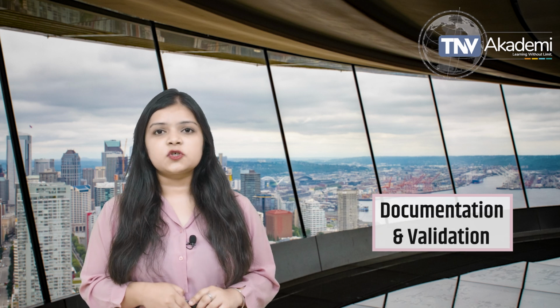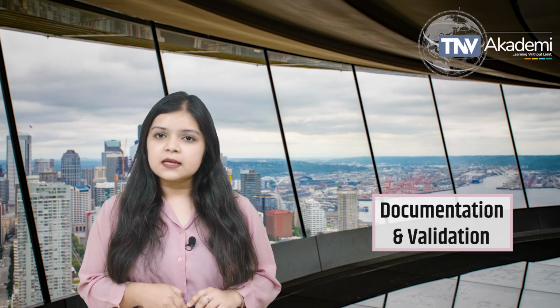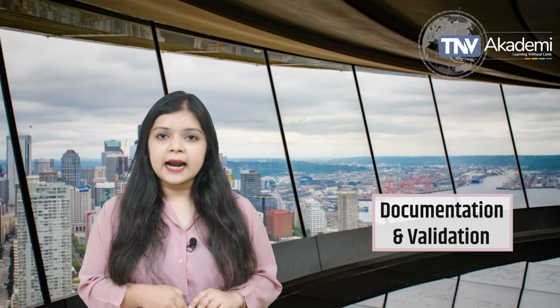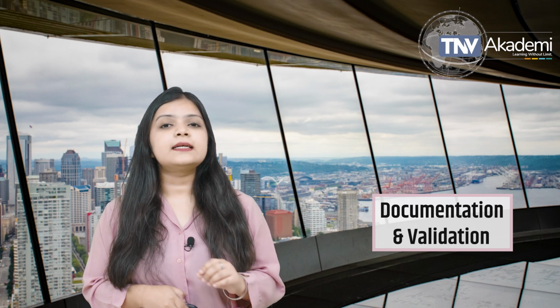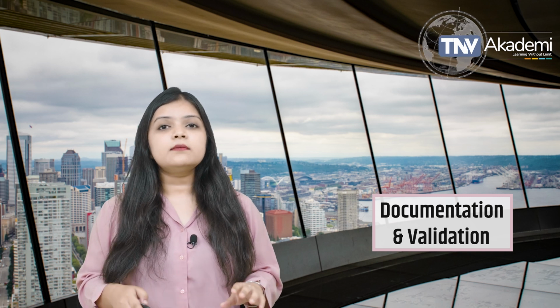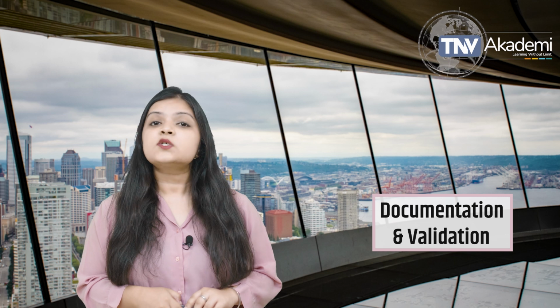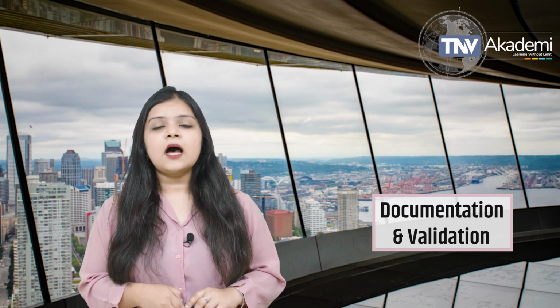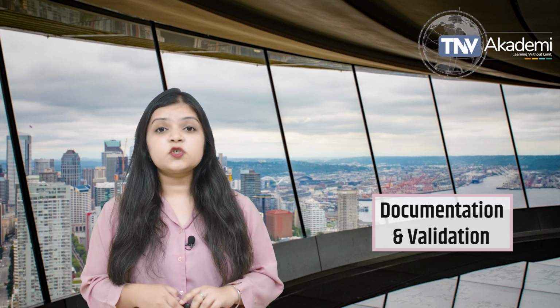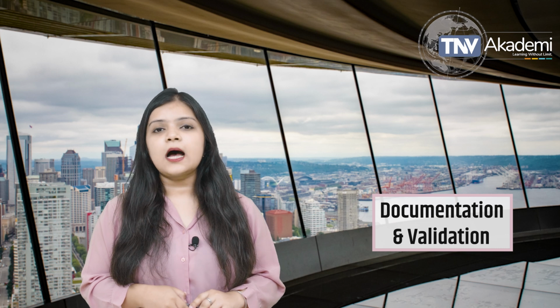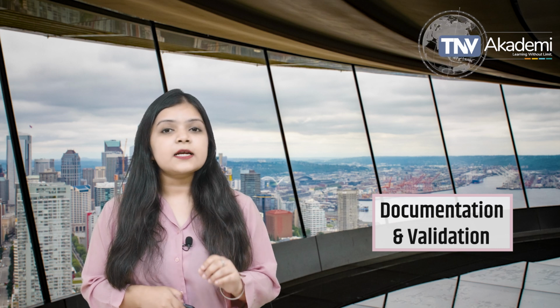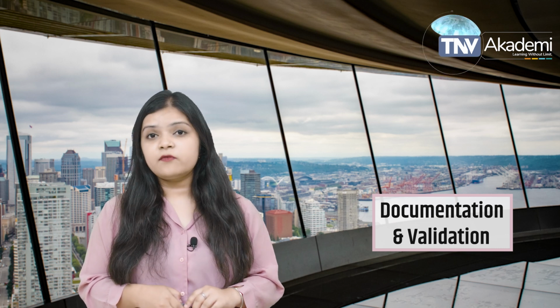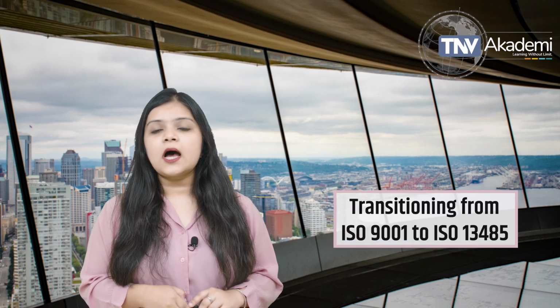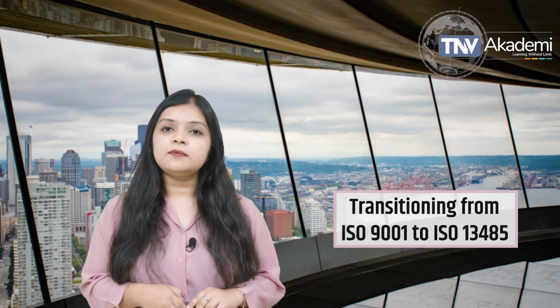Documentation and validation. Medical device companies must have stricter documentation and validation under ISO 13485, including records of regulatory approvals. So in simple terms, ISO 9001 helps businesses run efficiently, while ISO 13485 ensures that medical devices are safe, effective, and legally compliant. Transitioning from ISO 9001 to ISO 13485.